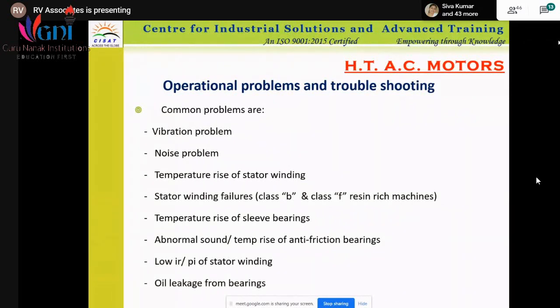Then various faults in the motor. Again, it is an electromechanical device. A transformer is static, while this is a rotating one. So we have problems with the static as well as the rotating system. Whatever faults are there in the case of the transformer, all these faults are available with the motor, except that there will be some rotational faults, like mechanical faults, vibrations, bearing failure. These are all rotational faults.